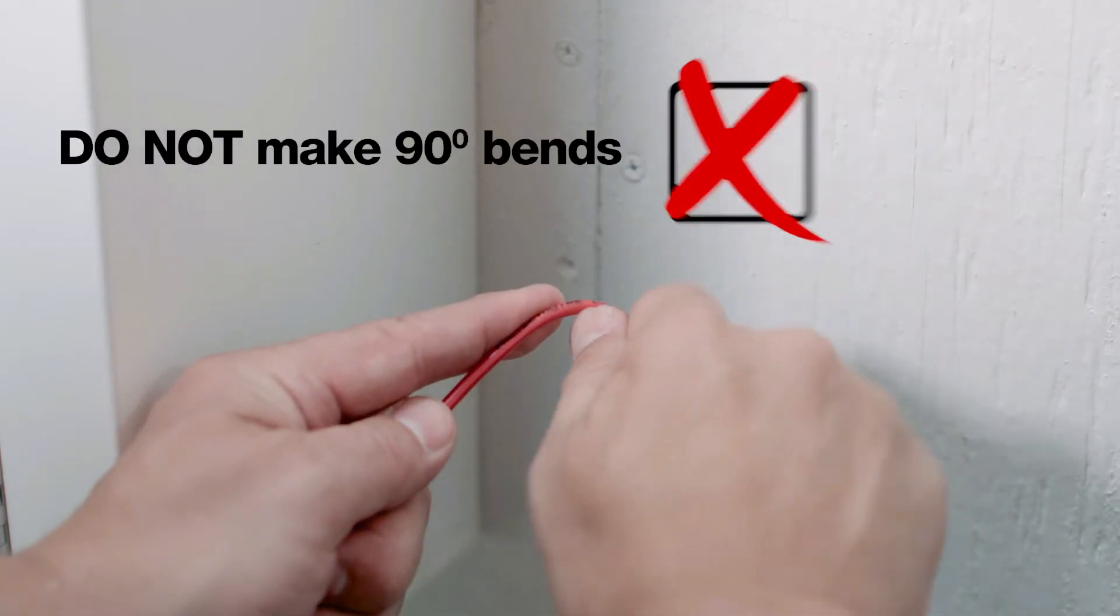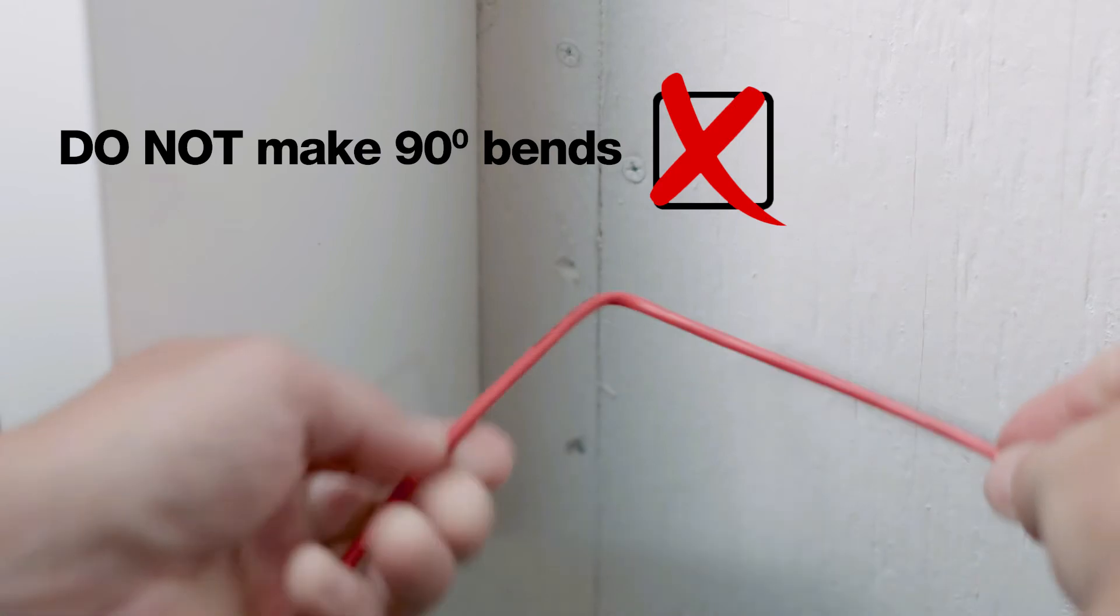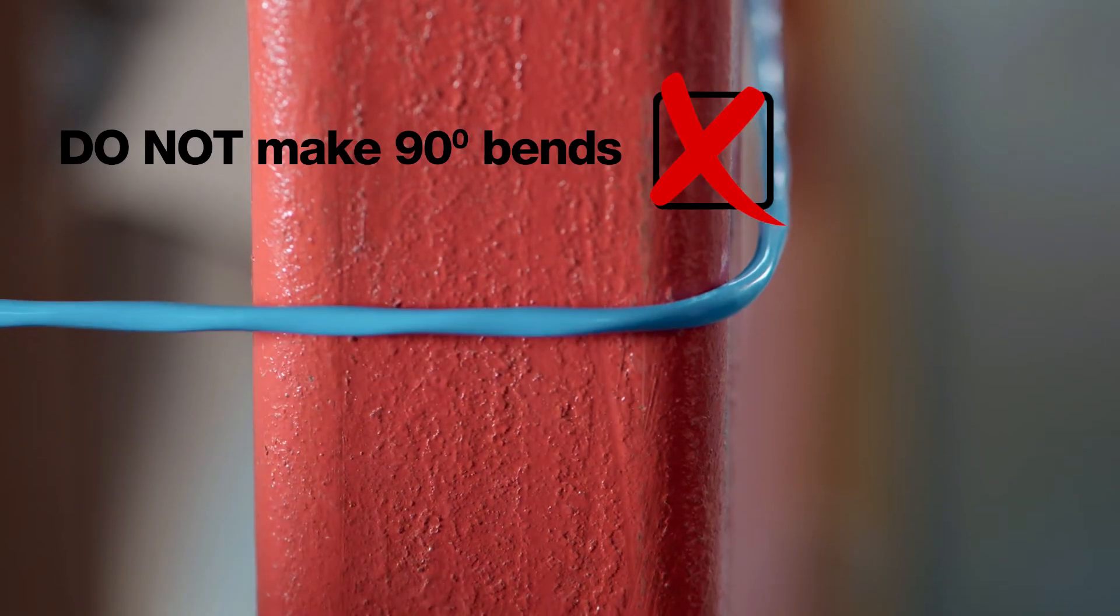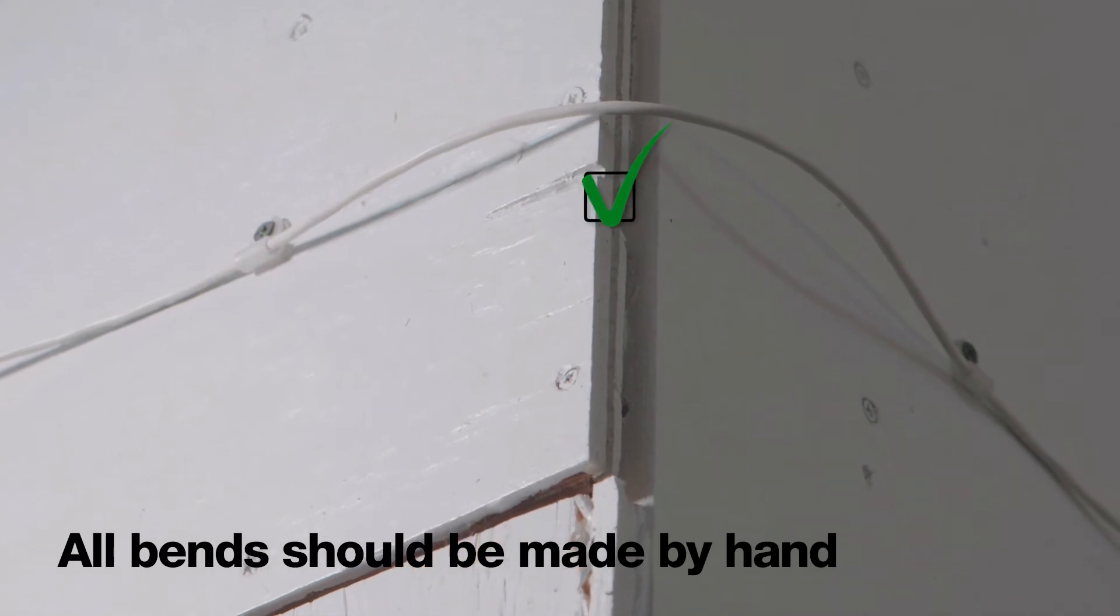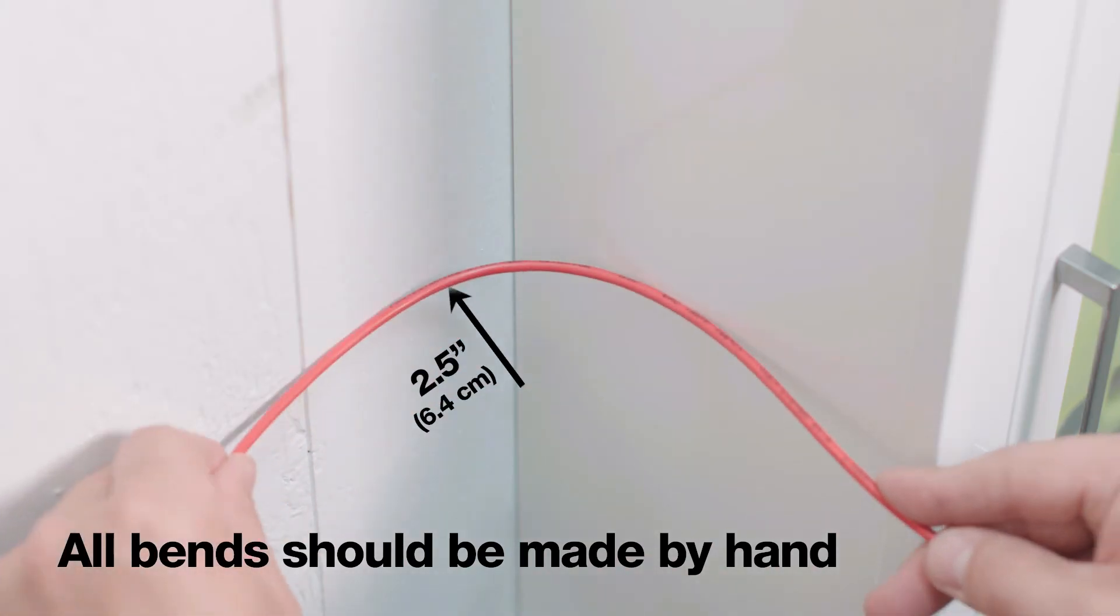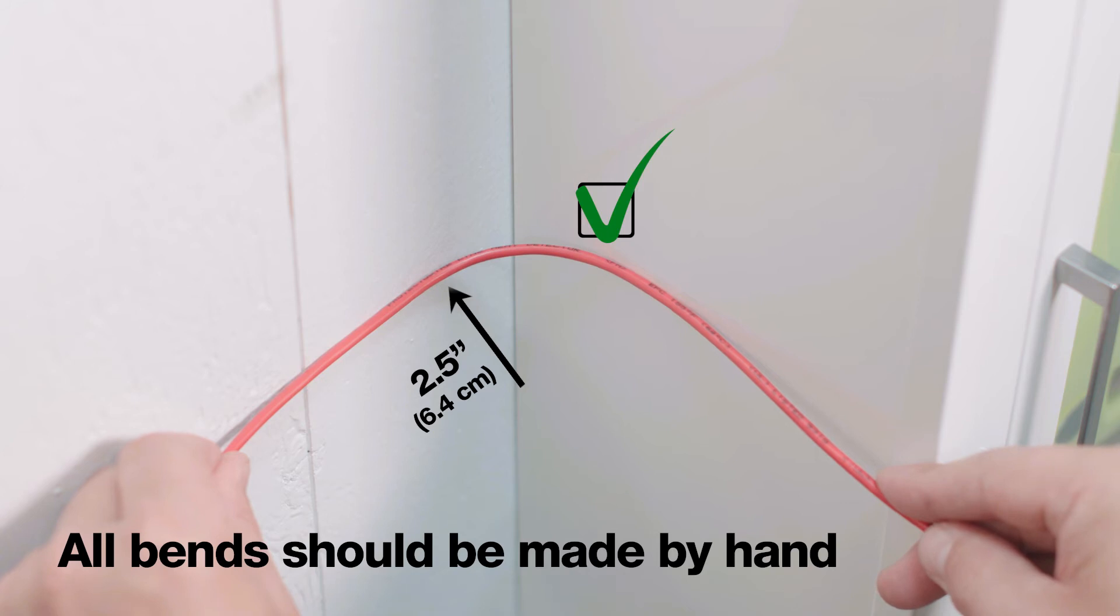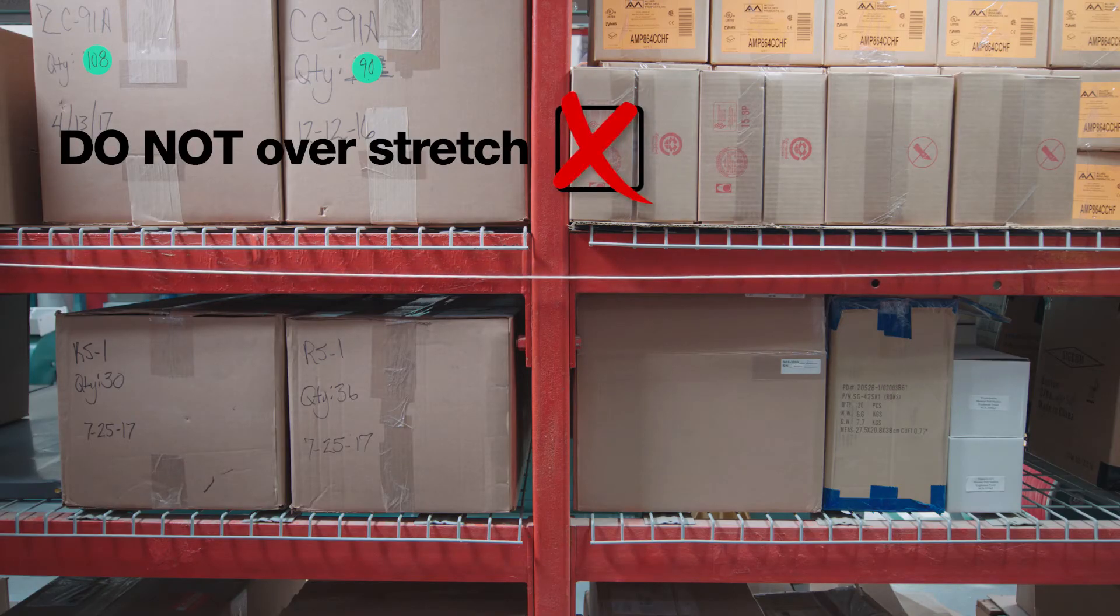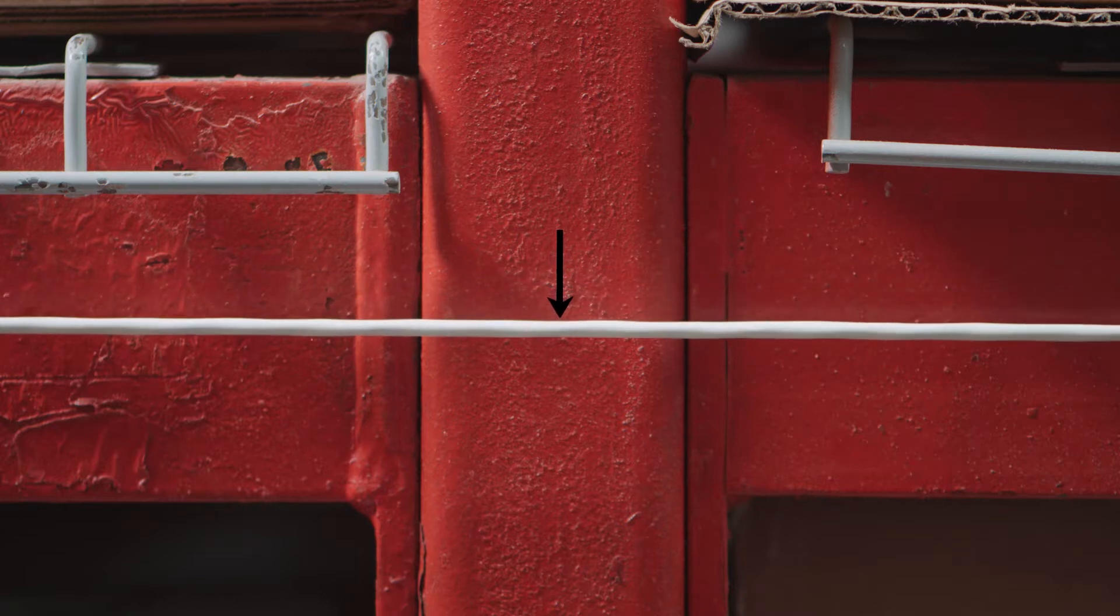Do not make 90-degree bends. All bends should be made by hand without the use of tools with a minimum two and a half inch radius. Do not over-stretch the detector runs. Some wire sag between fasteners is normal.